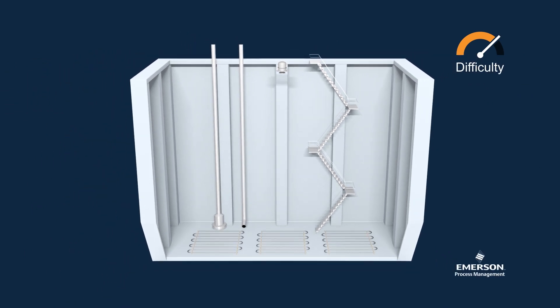When designing the tank, it can be necessary to locate heating coils, ladders and pipes within the radar beam area, causing radars to lock onto the disturbance echoes instead of the liquid.